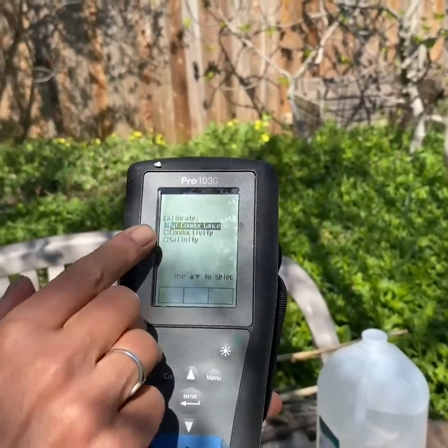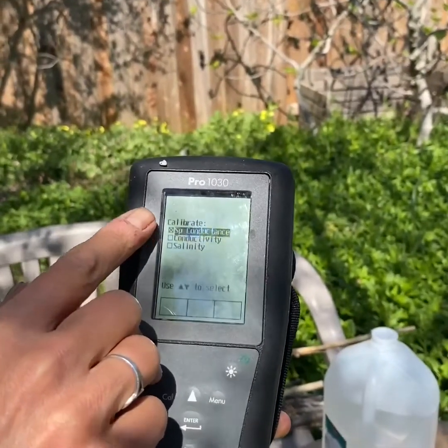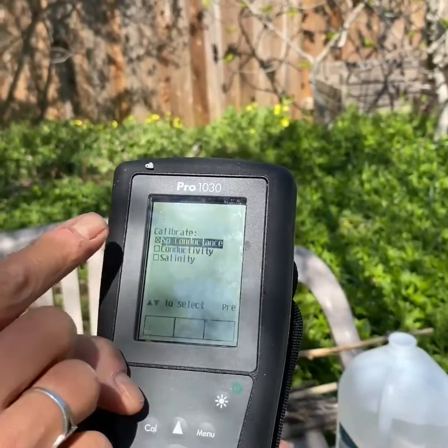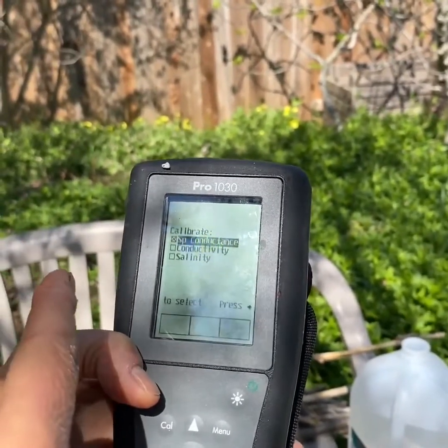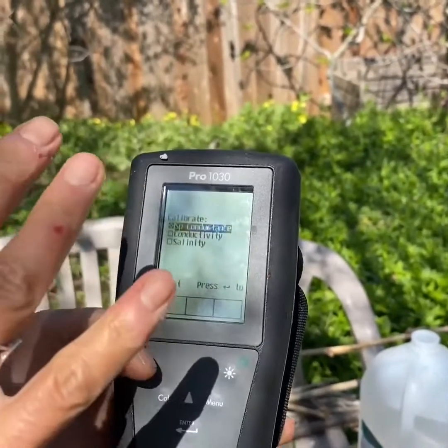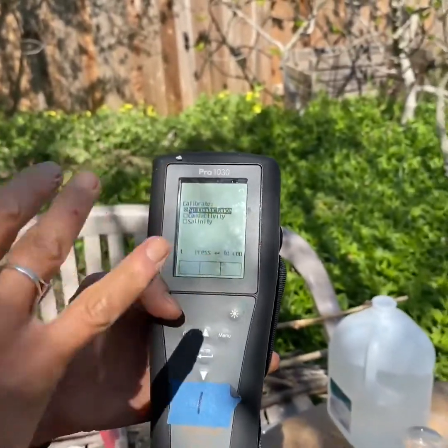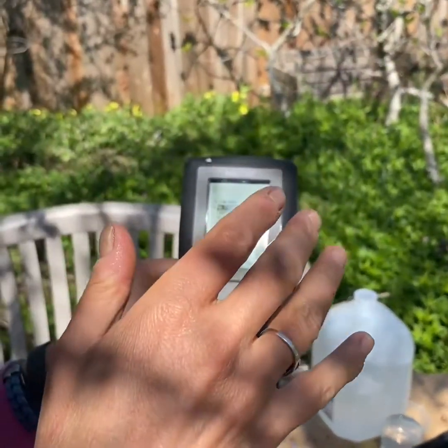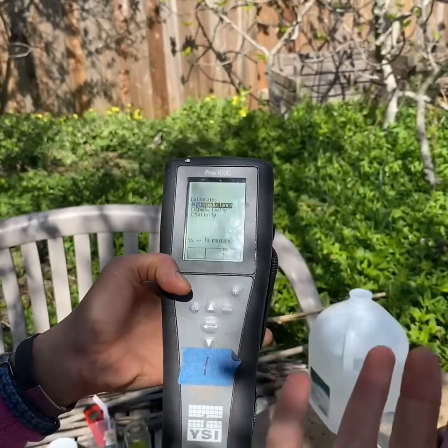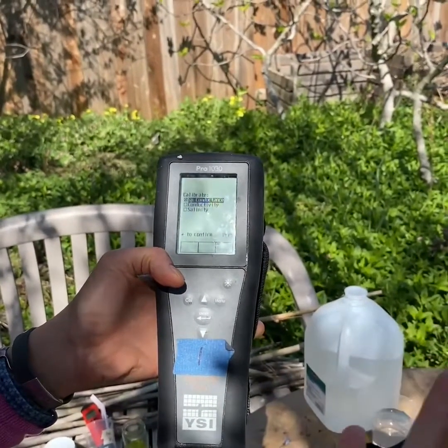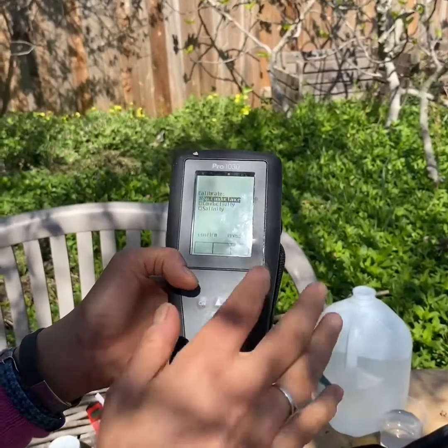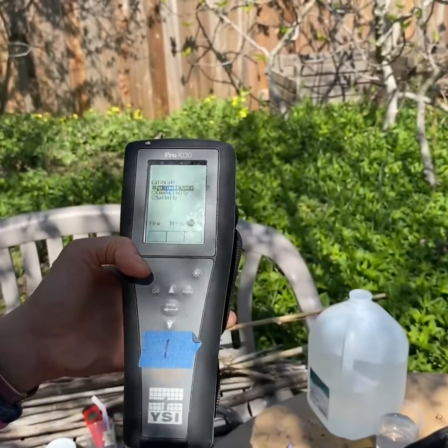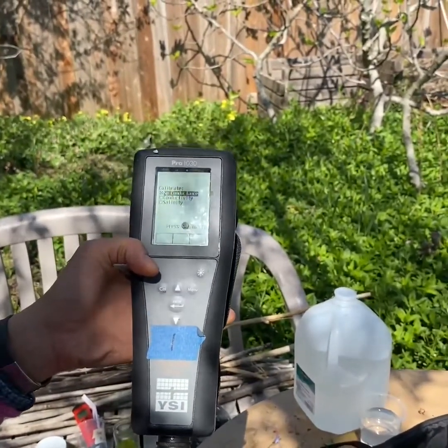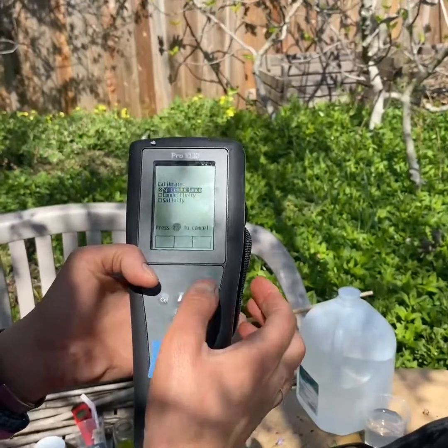And we're going to do the specific conductance. And so what specific conductance tells you is the electrical conductivity corrected for temperature. So it's going to tell us what the electrical conductivity would be if we were at 25 degrees Celsius. We might actually be kind of close to that here today, but that's what it will tell us for specific conductance.